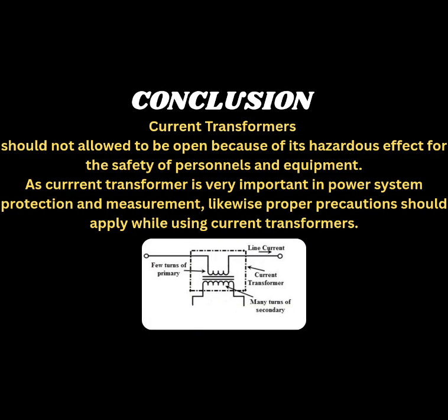In conclusion, leaving the secondary of a current transformer open-circuited is a hazardous practice that can lead to high voltages, risk of electrical shock, equipment damage, inaccurate measurements, and challenges for protection systems. It is crucial for electrical engineers and technicians to understand these implications and ensure that current transformer secondary circuits are always properly terminated with a load or relay, even when not in active measuring or protective use. Protective devices should include circuits that limit voltage and protect personnel from high voltage scenarios.